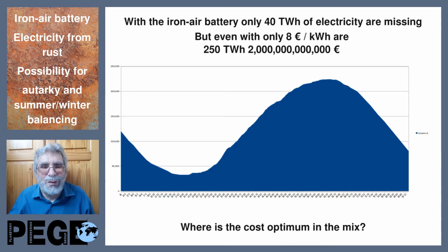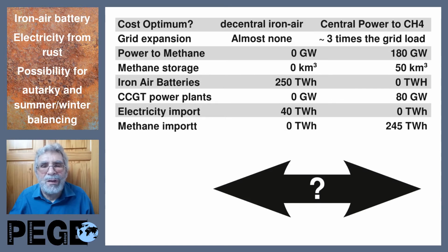But we have here 250 terawatt hours of batteries, and 250 terawatt hours of batteries times 8 euro per kilowatt hour is 2,000 billion euros. So maybe there is a possibility to mix both systems for a cost optimization. We have these two systems. We have decentral iron-air and central power to methane.